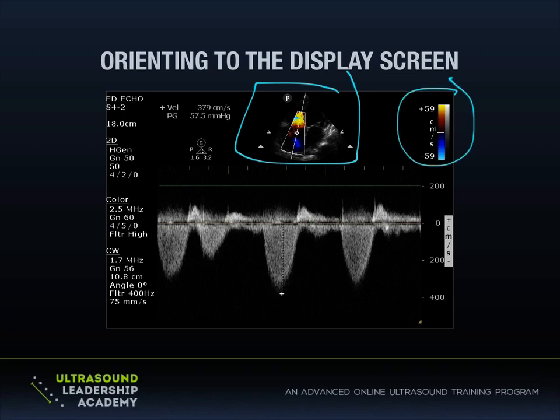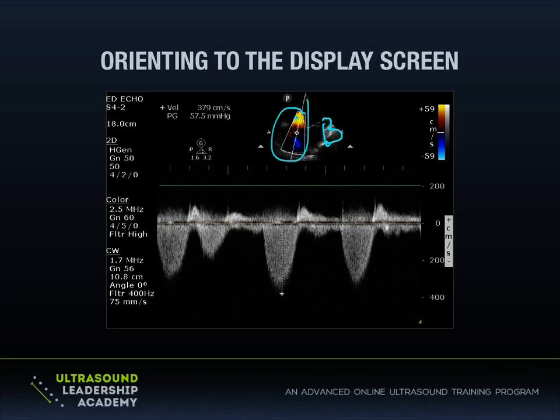Now, what we're doing in this screen clip, though, is actually something called triplex imaging or spectral Doppler, where we have a B-mode image here, so just the grayscale image in the background. We have a color image on the top, and then we've applied Doppler to it as well, in this case, continuous wave Doppler. And the continuous wave Doppler, which is featured down here, plus the color, plus the 2D is 1, 2, 3, and is either known as triplex as opposed to duplex with two modes, or spectral Doppler.